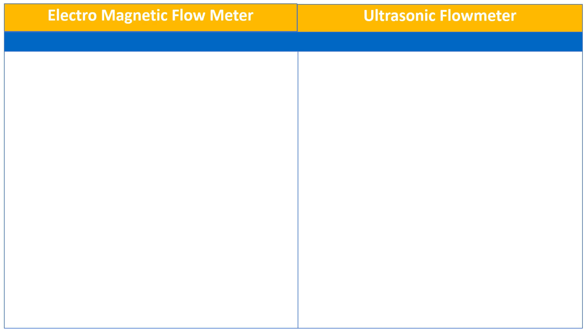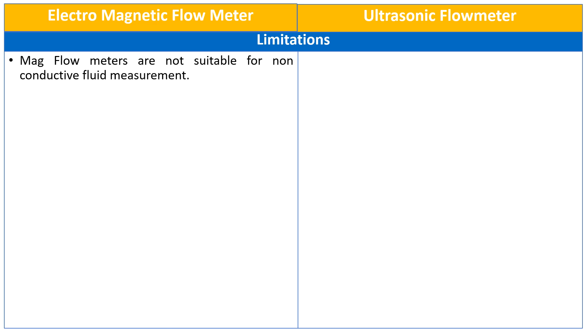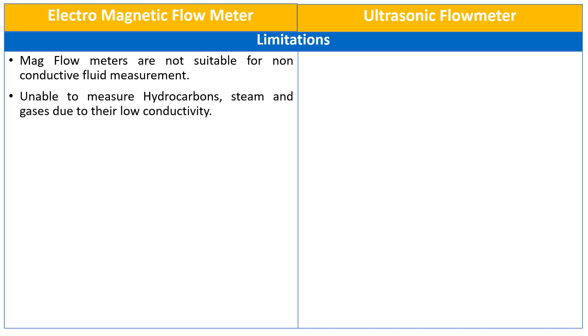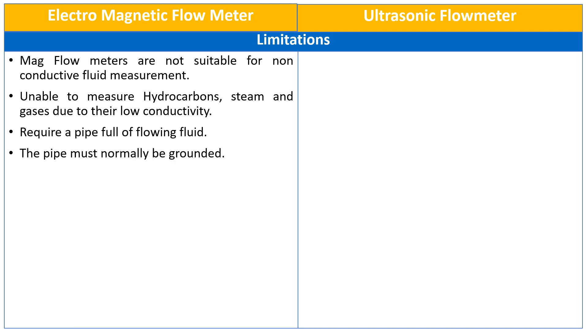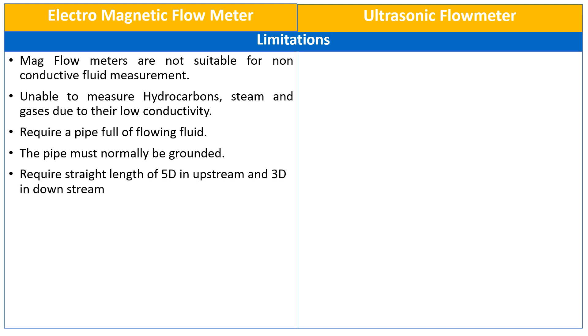Both the electromagnetic and ultrasonic flow meters have some limitations. The electromagnetic flow meters are not suitable for non-conductive fluid measurement. They are unable to measure hydrocarbons, steam, and gases due to their low conductivity. They require a pipe full of flowing fluid. The pipe must be normally grounded in case of an electromagnetic flow meter. The electromagnetic flow meter requires a straight length of 5D in upstream and 3D in downstream.